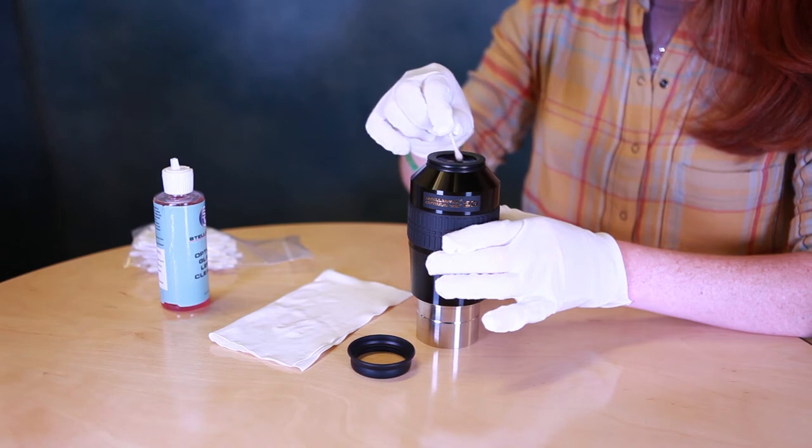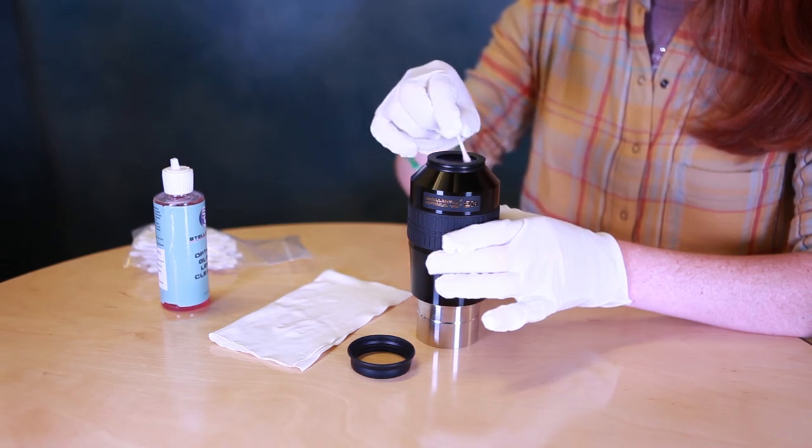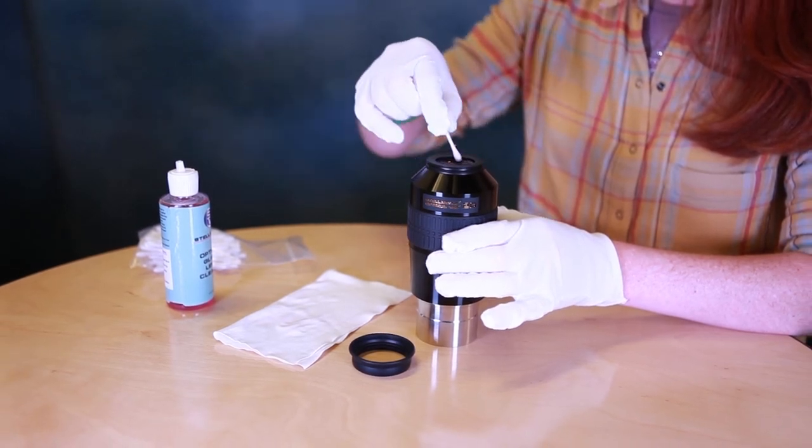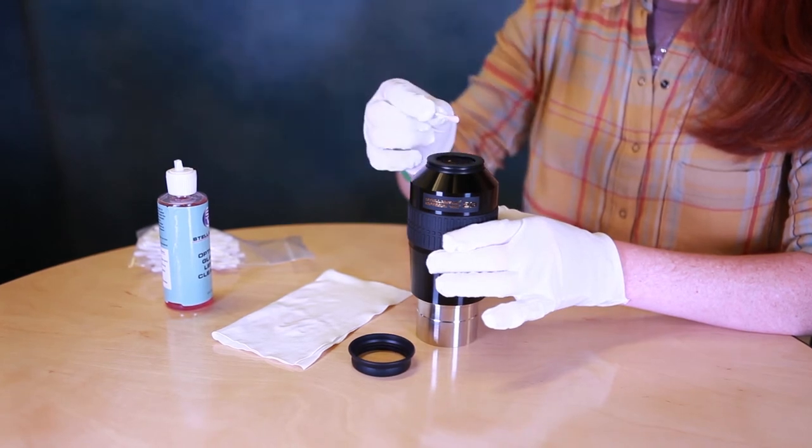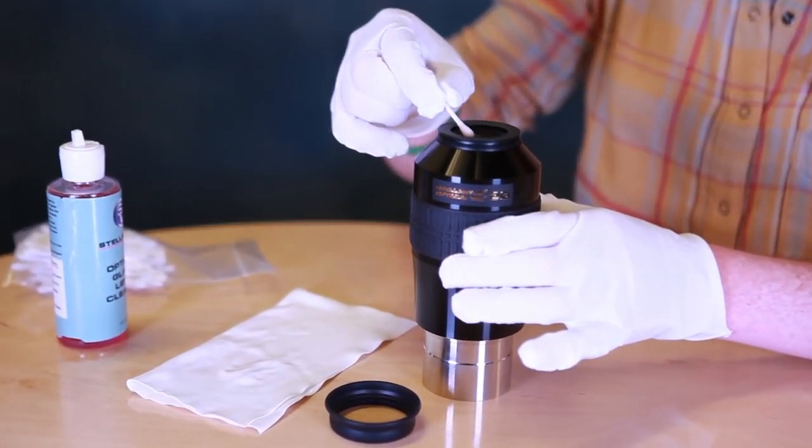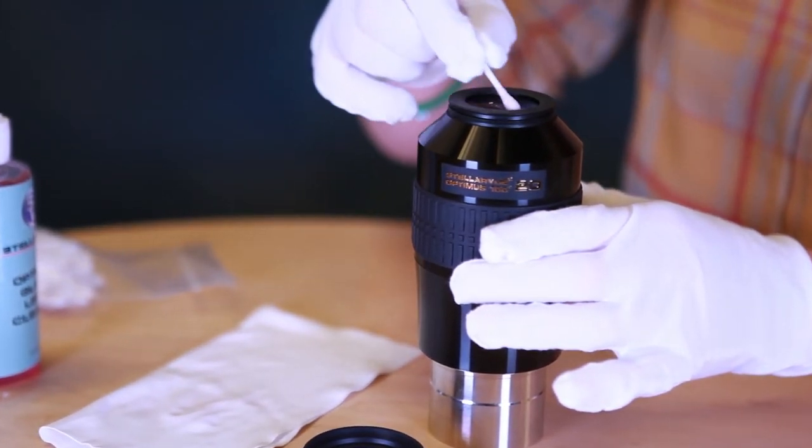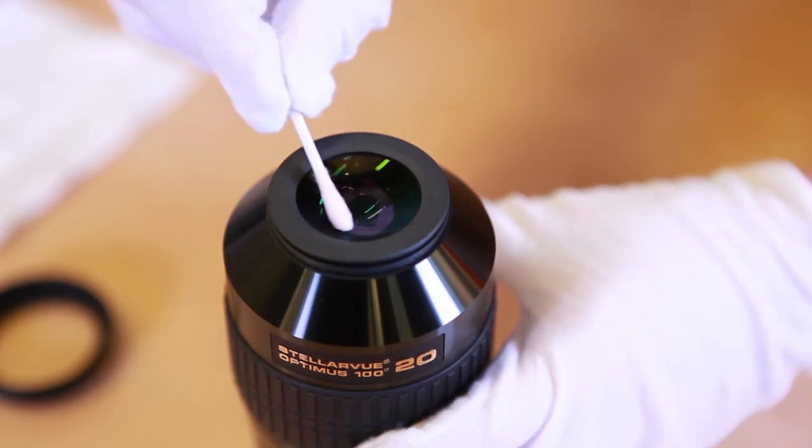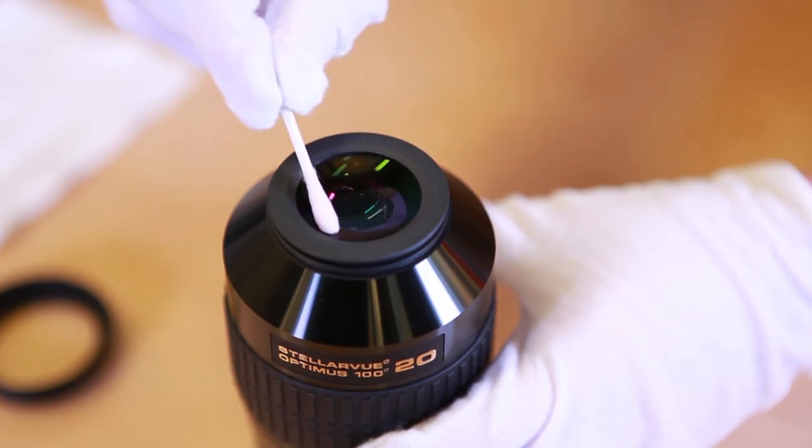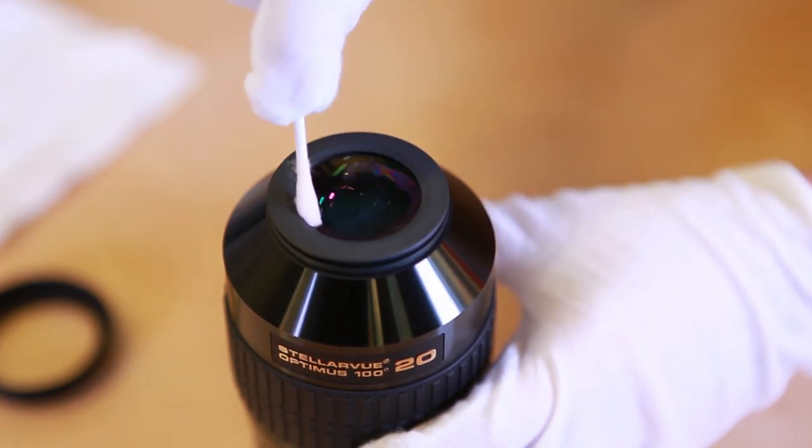When you clean the lens surface, start in the center. Go in small circles and work your way slowly out towards the edge. Do this three times. Each time, you rotate the cotton swab one third turn before doing it again.